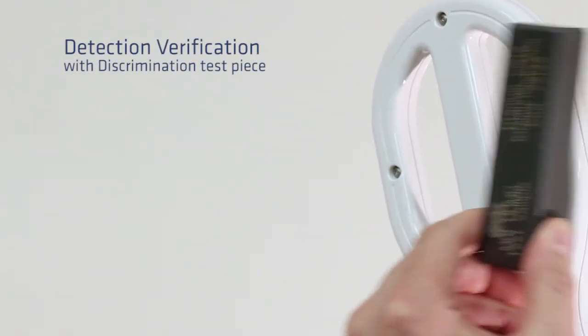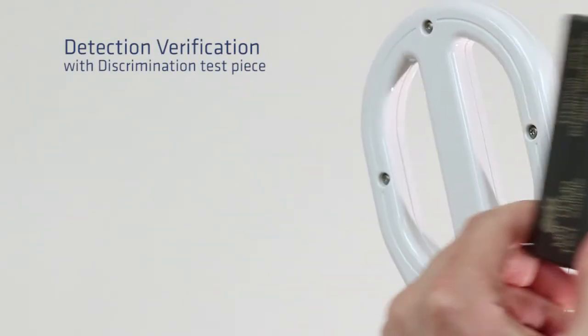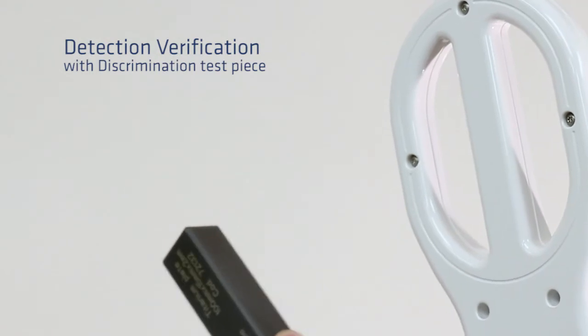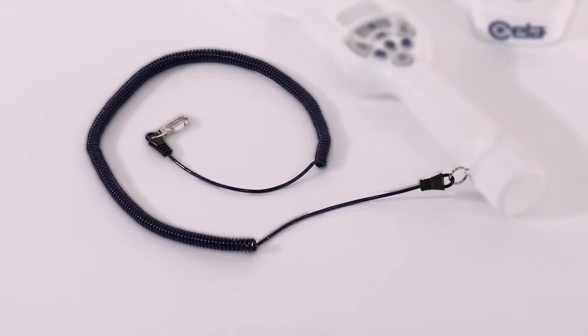Then pass the titanium plate discrimination test piece close to the bottom side of the detector. Make sure the test piece passes over the center point of the sensing area and that it triggers an alarm. An optional tether is included with the kit. The purpose of the tether is to prevent the device from being left on a hospital transport device and having it enter MRI Zone 4. Using the tether is not a requirement for operation of the device.